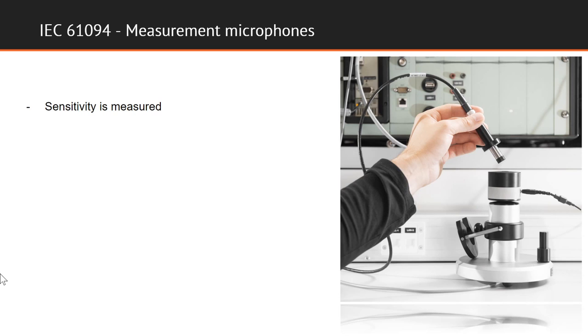The sensitivity of the microphone that is being calibrated is measured by comparison with the reference microphone. The two microphones are exposed to the same sound pressure in an active comparison coupler, which contains a built-in sound source. The measurement frequency can be set to either 250 Hz or 1 kHz. The measured sensitivity is, however, valid at the environmental conditions during the measurement. Correction is made for the influence of environmental pressure, temperature, and humidity on the reference microphone.